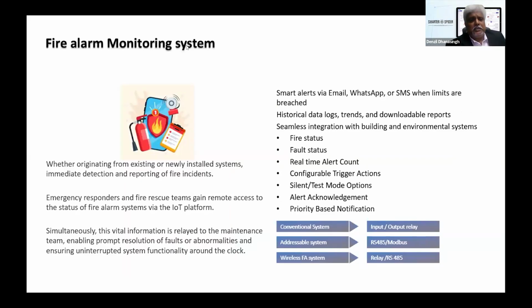So when the existing system is a conventional system, what do you do? Is it possible to take it? Yes, it is possible. There are relays available from your conventional system. Through those relays, we can take the inputs to our gateway. If it is an addressable system, usually they will have Modbus or RS485 or TCP/IP connectivity. So we can easily get the addressable system alarms also through the gateway. And again, wireless is similar to a conventional system where relays can be used, or some panels can have RS485, which can also be used to transmit the data.